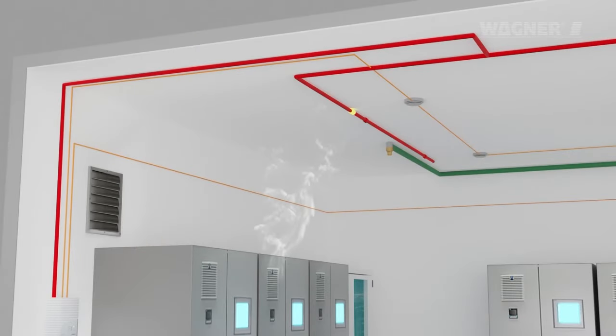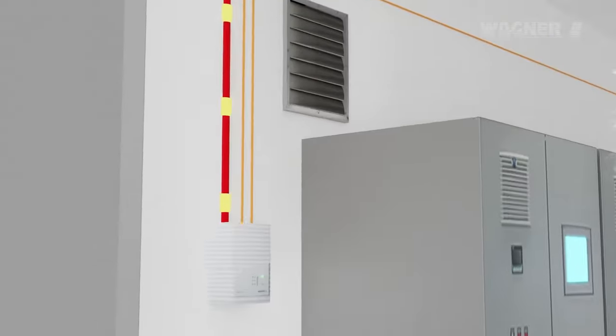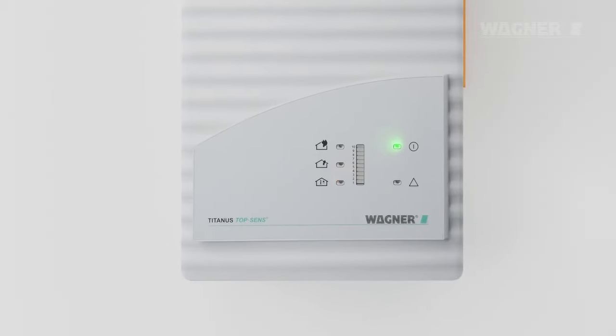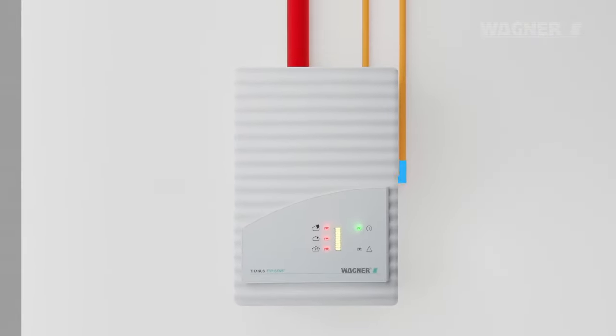In the event of a developing fire, even the smallest smoke particles should be aspirated by the aspiration pipe system and fed to the Titanus aspirating smoke detector so that a fire can be detected at an early stage.